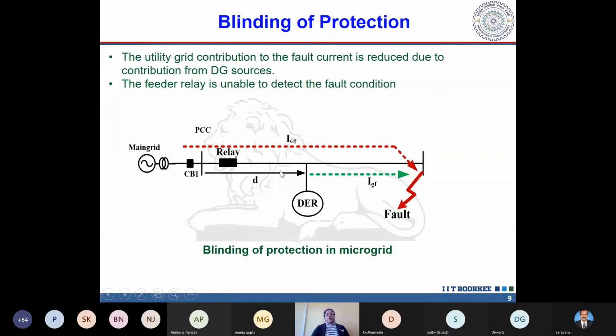So due to this DER presence, the relay will see just 8 ampere instead of 10. This is just an example, and this magnitude may fall below the threshold as well, isn't it? Then the relay will not say that there is a fault, and it will not generate any trip signal for opening the circuit breaker. This is known as blinding. The meaning of blinding is that even though there is a fault, the relay is not able to trip the line.